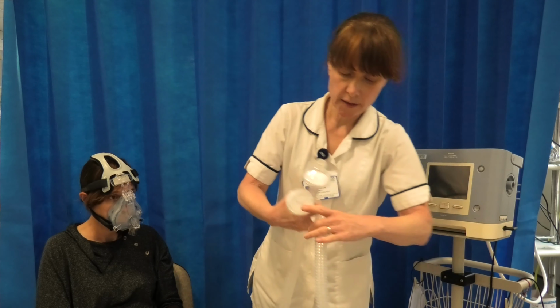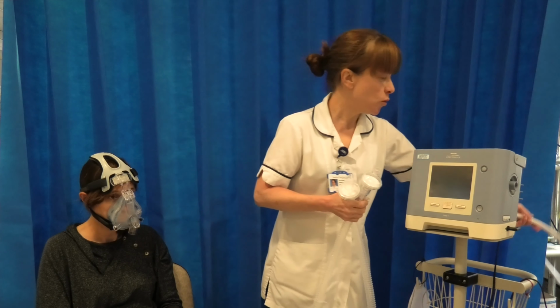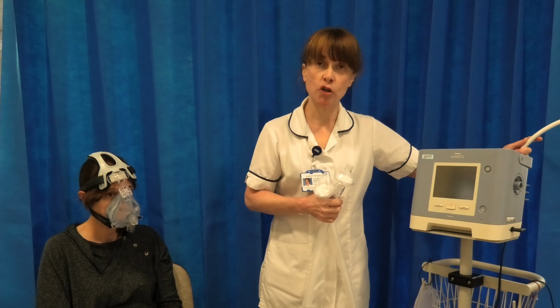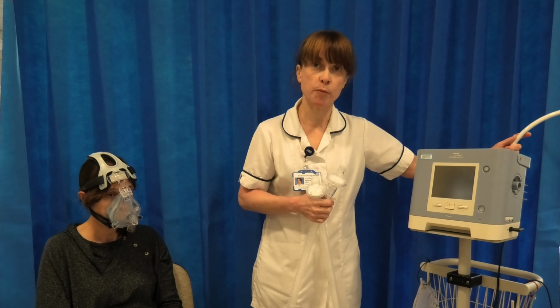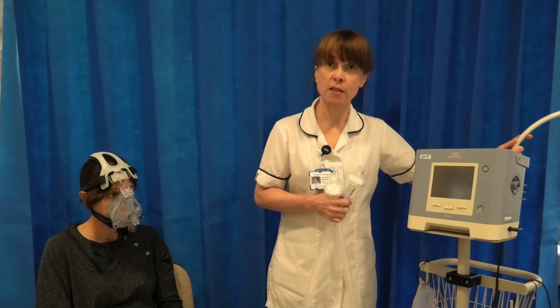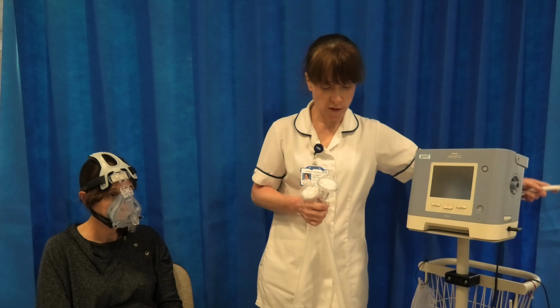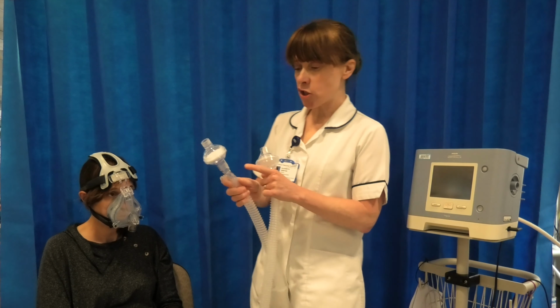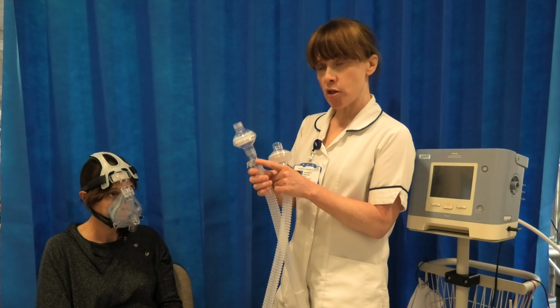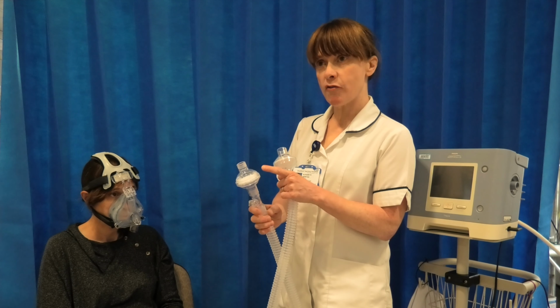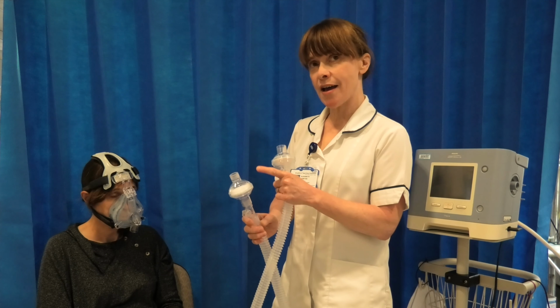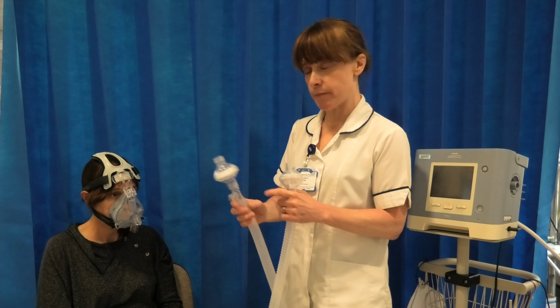and discard it. Now the Trilogy 202 has a high pressure oxygen inlet, so you can deliver between 21 and 100% oxygen, so you need to make sure that's plugged into the oxygen port in the wall. So at the patient end you have your exhalation port. Before the patient you always have your filter, so both inhaled and exhaled gas are filtered.